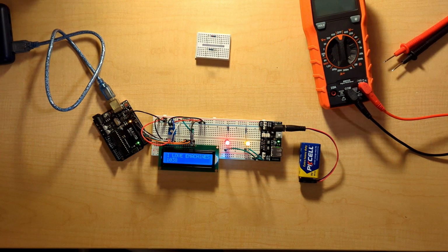Especially when locking out a circuit, it's common practice to perform a dead live check with your meter. This means testing the meter on the energized circuit to confirm the readings on the meter, locking out or de-energizing the circuit and confirming that there is no power, and then testing the meter again on a known live source to confirm that your meter is giving reliable readings.